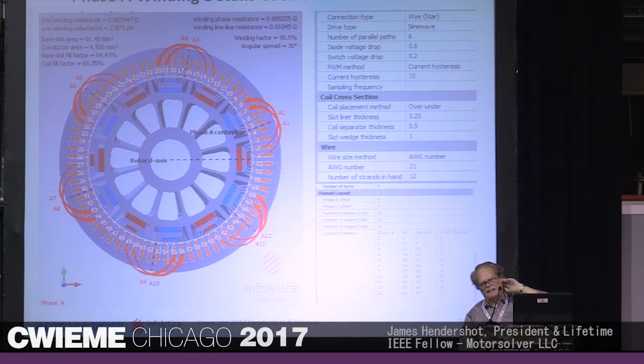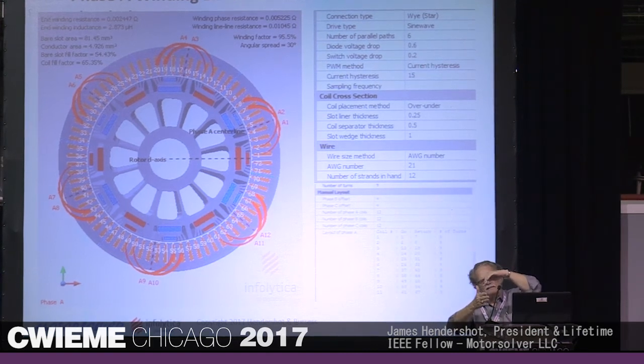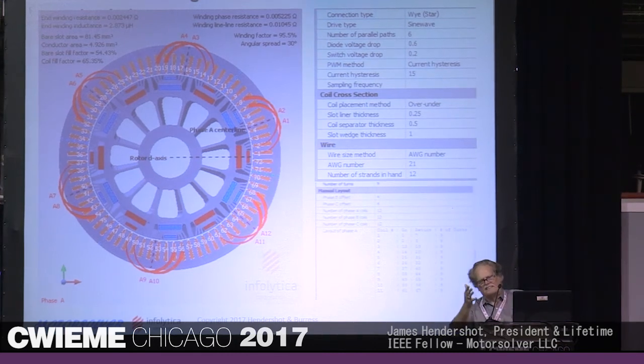Then, as part of winding factor is the skew factor. If you skew the magnets, if you skew the flux, then that reduces the distribution. Because if all the poles are in line on that 12-4, all the conductors are right in the center, my winding factor's unity. But if I skew that, they're not all centered anymore, because it's only centered as you rotate it. So that reduces your winding factor. These softwares calculate all that stuff. Everybody's does, I guess.